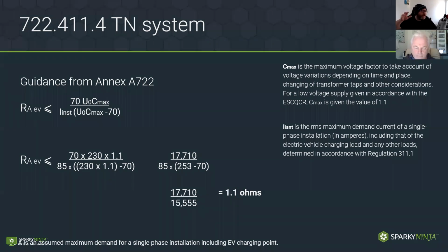Now, does that sound familiar? A factor for voltage variations due to transformer taps, etc. But this is not a Cmin, this is a Cmax. So unlike in Part 4, where we went with a Cmin to consider the potential of a drop in voltage, which would achieve insufficient current for ADS, here we want to make sure we have no more than 70 volts, so we've got to consider the potential maximum voltage. So what the Cmax does, you can see the factor here is 1.1, is in the formula it changes the 230 to the peak of that, which I think is 256. Oh, sorry, 253. It pushes it to the peak voltage that we have allowed in our voltage range in BS 7671. That's a little tweak to this from the previous edition.